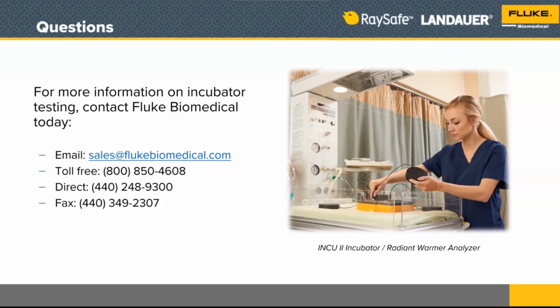What we would do is say, all right, so I can't get an 11 degrees C rise, but I can get some rise, right? From my ambient temperature to my set point. And I would just document what I can get. I might put a statement in my medical device quality assurance program that says, in our country, when we don't have a cool environment to shop in with air conditioning, then we will document the rise to the set point from whatever our ambient is. And that's what we're going to document. And yes, we understand it doesn't specifically meet the standards.